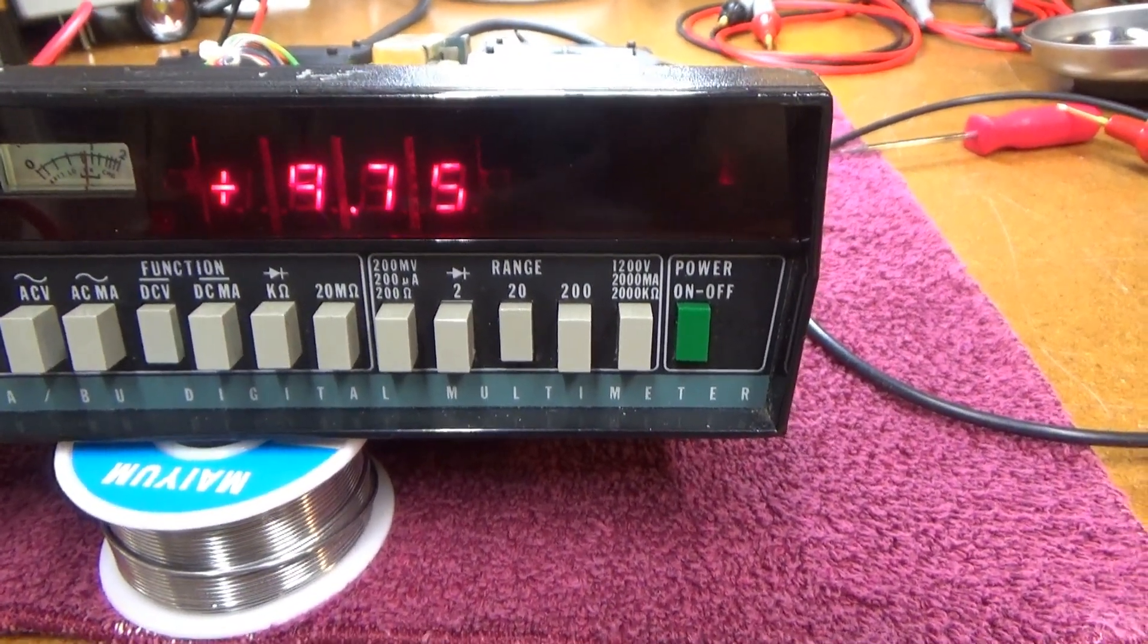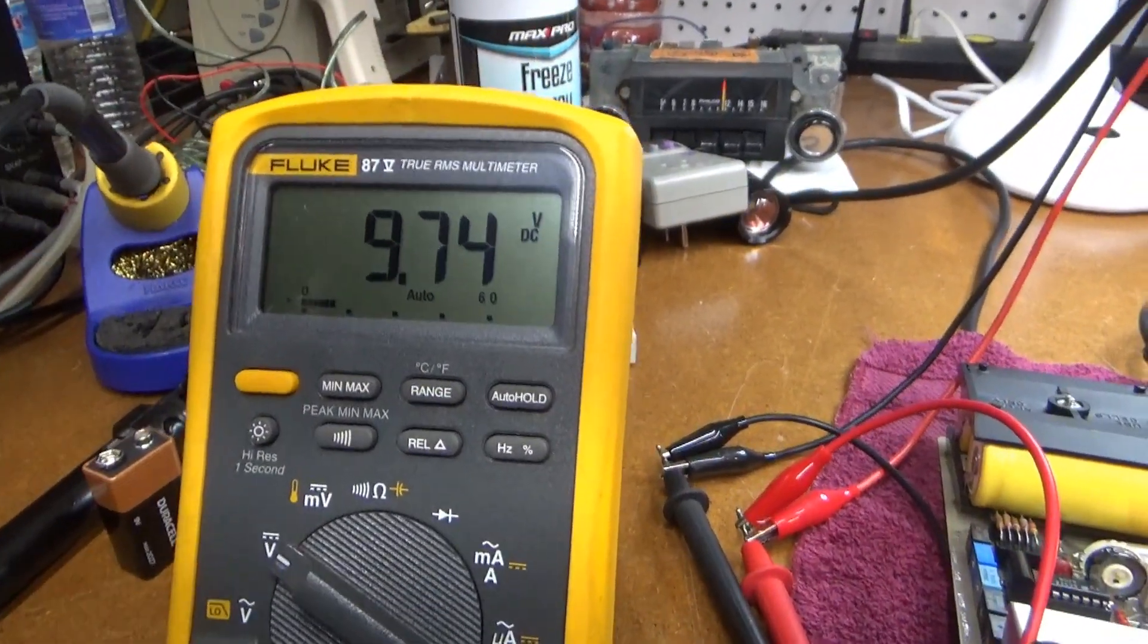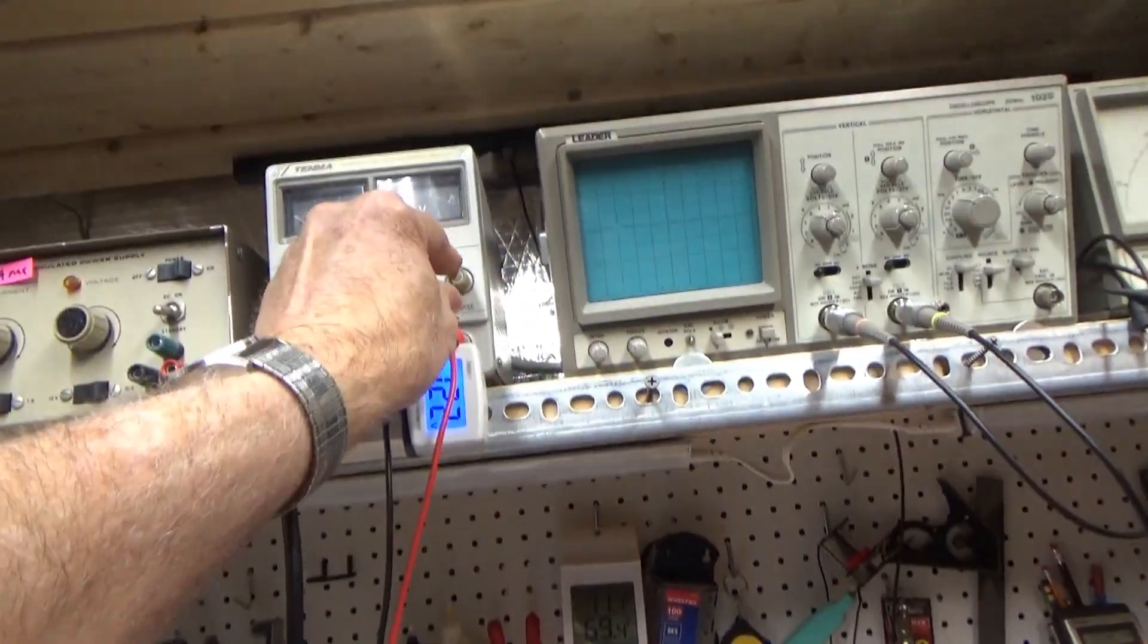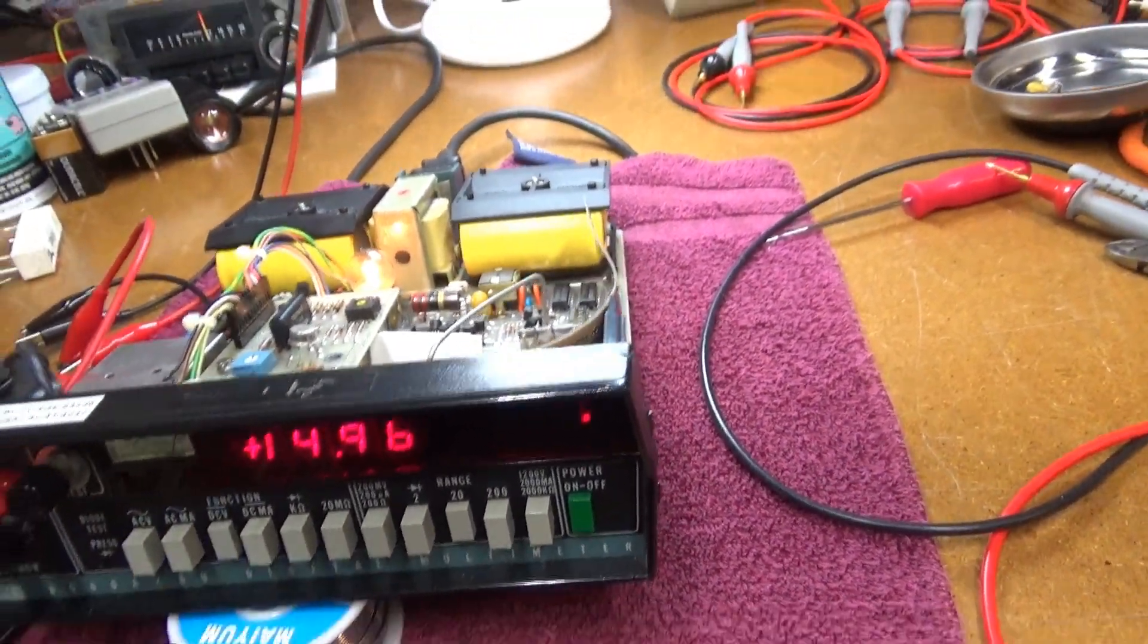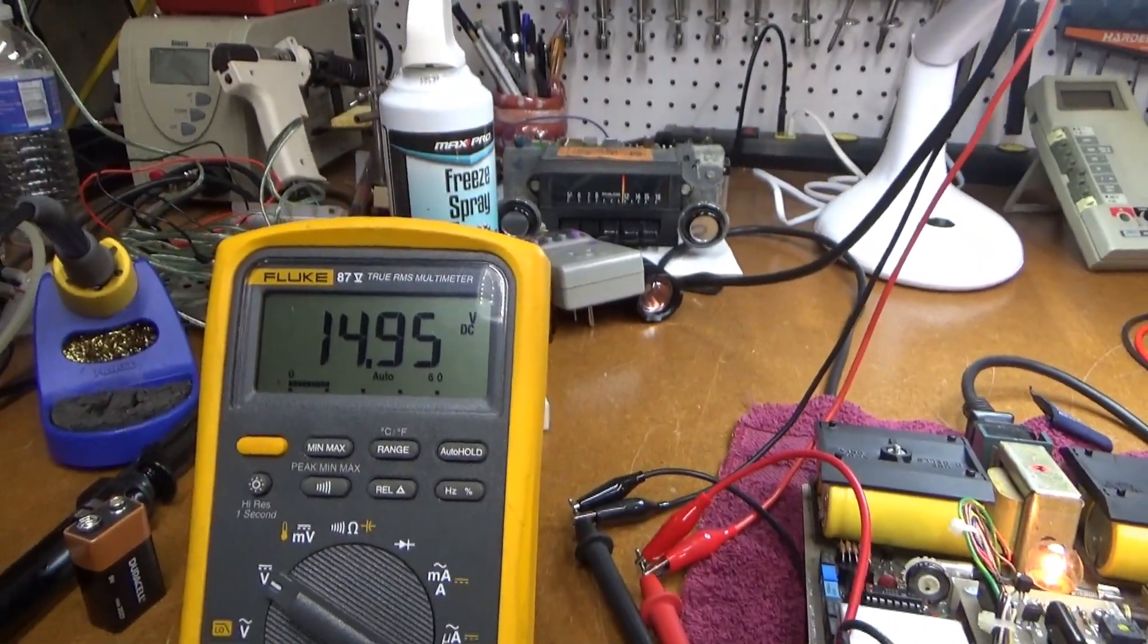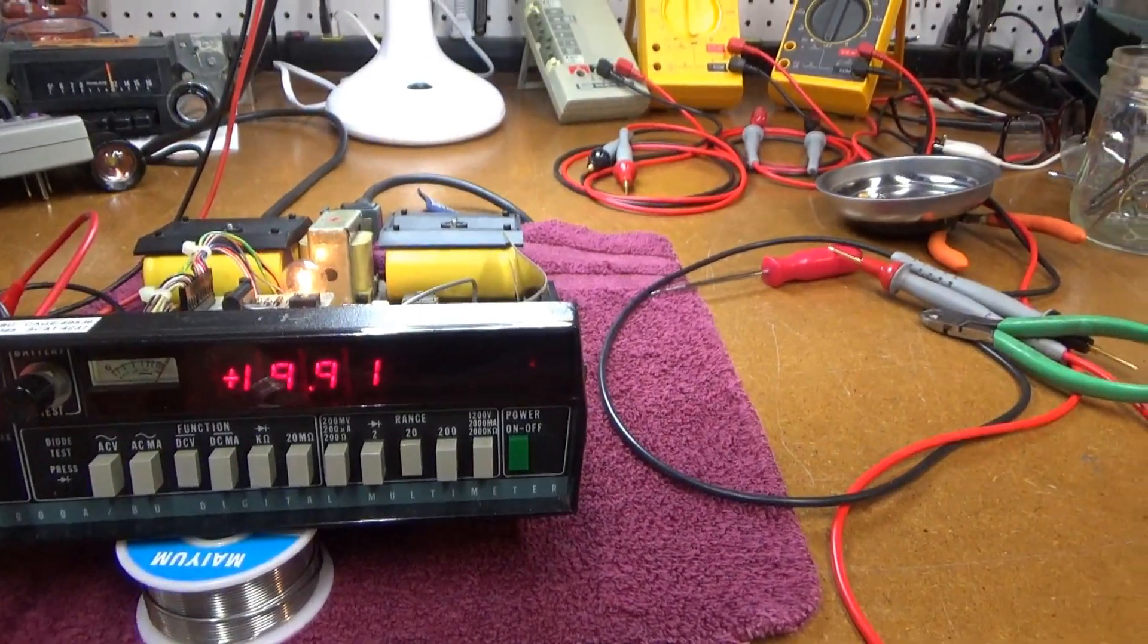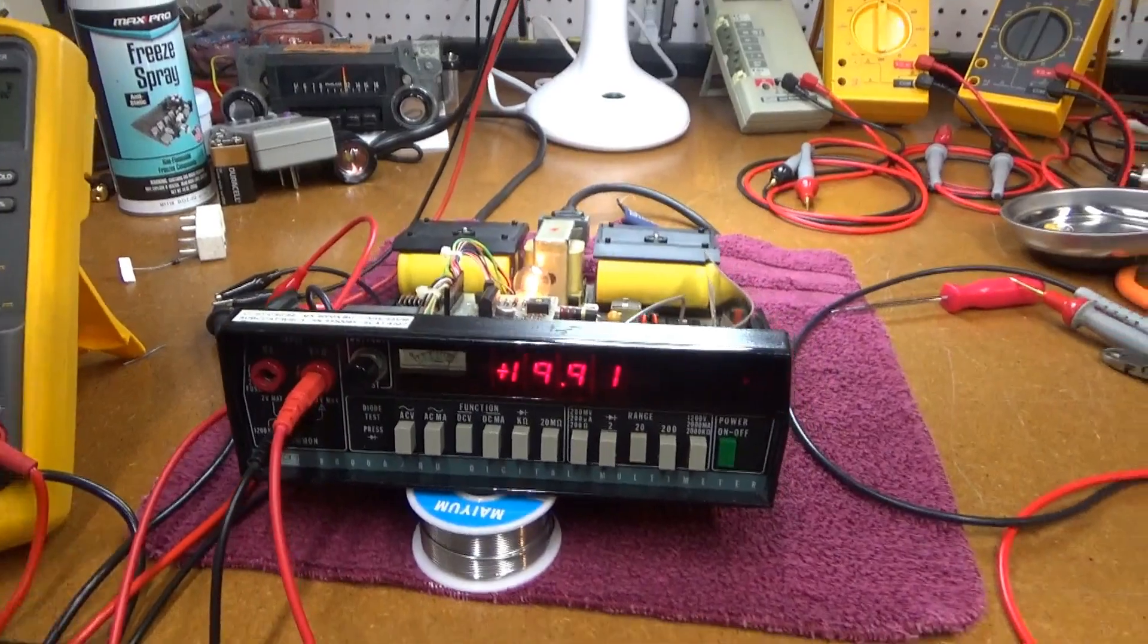It's measuring 9.75, and the Fluke is 9.74. So let's try cranking up the voltage here a little bit on that. Let's go up to about 15. 14.96, 14.95. A little bit more. There should be about 20. 19.91, 19.90. Wow, pretty good.